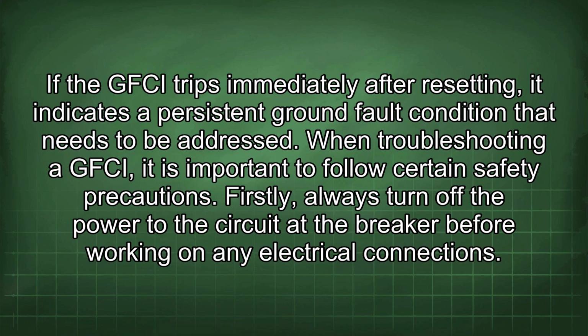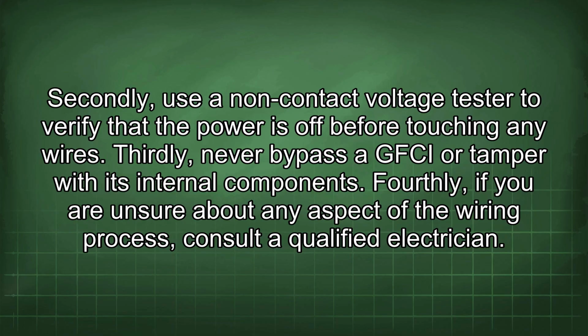When troubleshooting a GFCI, it is important to follow certain safety precautions. Firstly, always turn off the power to the circuit at the breaker before working on any electrical connections. Secondly, use a non-contact voltage tester to verify that the power is off before touching any wires. Thirdly, never bypass a GFCI or tamper with its internal components. Fourthly, if you are unsure about any aspect of the wiring process, consult a qualified electrician.